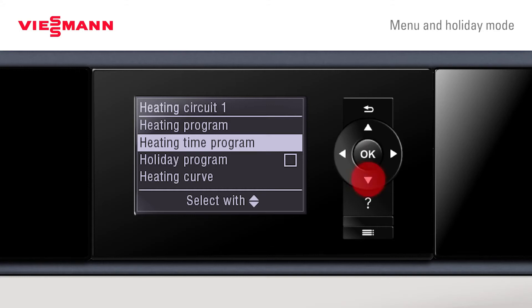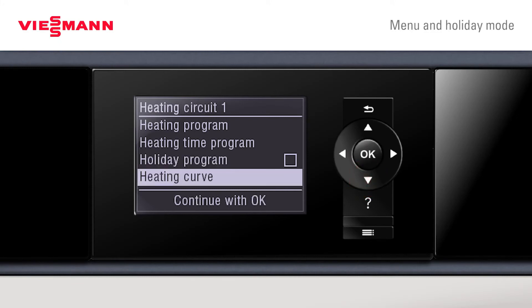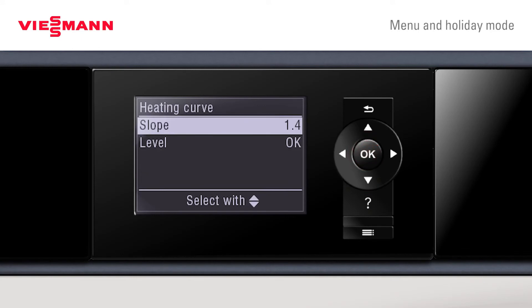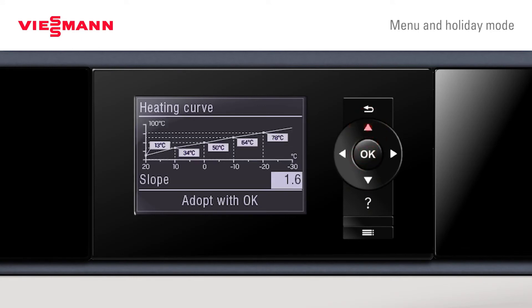After setting the heating program, there are further options including a holiday program, which keeps the boiler on standby until you return from holiday and brings the boiler on the day before. There is also a heating curve setting where you can set the slope or level, shown in pictorial form on screen.